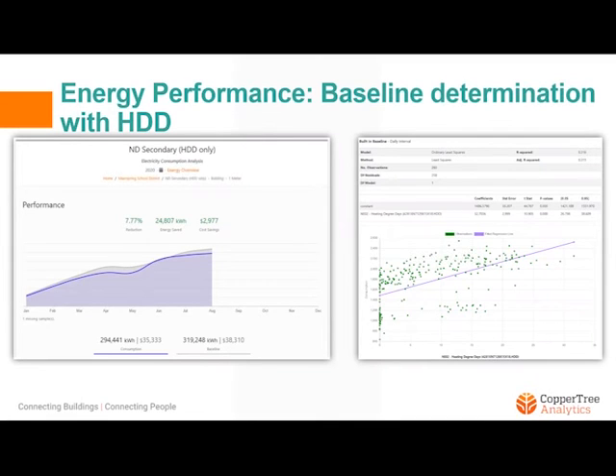What you're looking at here is a screen capture from CopperTree's EIS tool, the Energy Information System tool. And we are trying to determine the baseline energy consumption for a building. It's a school building. You're looking at the electricity consumption in purple on the left-hand side of the screen. And the gray line is the baseline, which was calculated using an independent variable, heating degree days, which you can see on the right-hand side of your screen. That linear regression analysis was completed. The R-squared value was not very good, meaning it wasn't really following each other all that well. However, the results showed that there was a 7.77% reduction in energy consumption, which translated to close to $3,000 in cost savings.